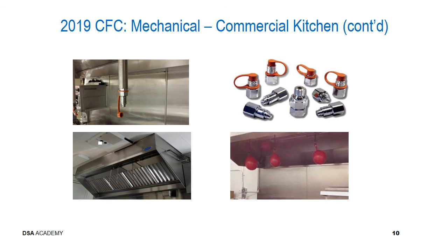Inspectors shall ensure the correct nozzle sizes are used as shown on the DSA-approved plans, specifications, and manufacturer's design and installation manual. After testing is complete, ensure that the rubber covers, the grease caps, are securely replaced over the nozzles, and that the system has been restored to service. It is important to verify that the proper temperature-rated fusible link has been provided.